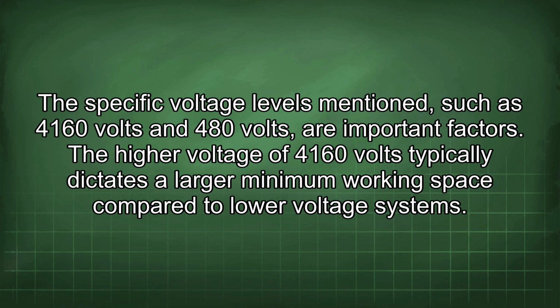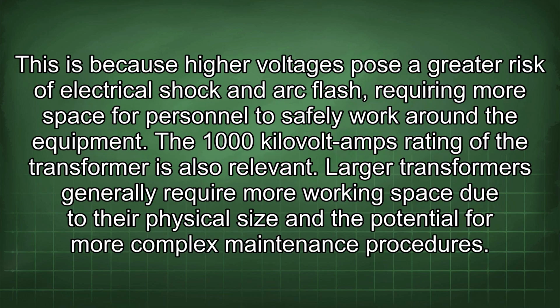The higher voltage of 4160 volts typically dictates a larger minimum working space compared to lower voltage systems. This is because higher voltages pose a greater risk of electrical shock and arc flash, requiring more space for personnel to safely work around the equipment. The 1000 kVA rating of the transformer is also relevant. Larger transformers generally require more working space due to their physical size and the potential for more complex maintenance procedures.